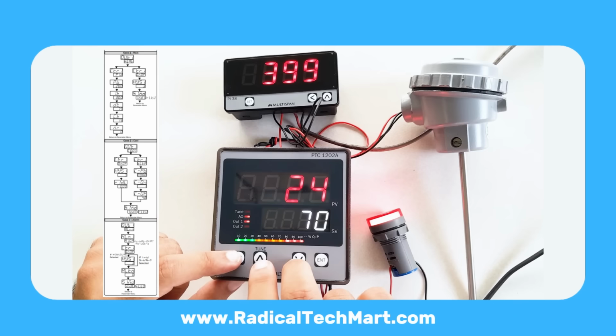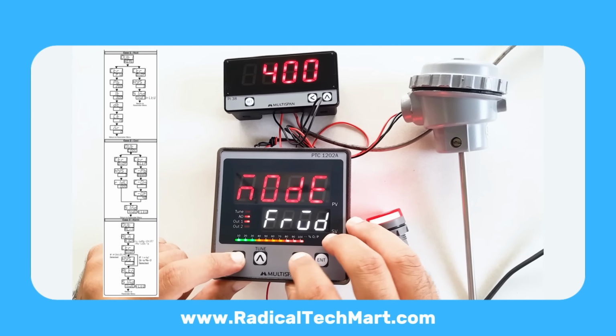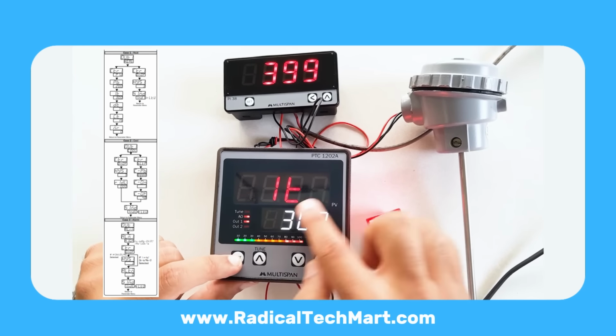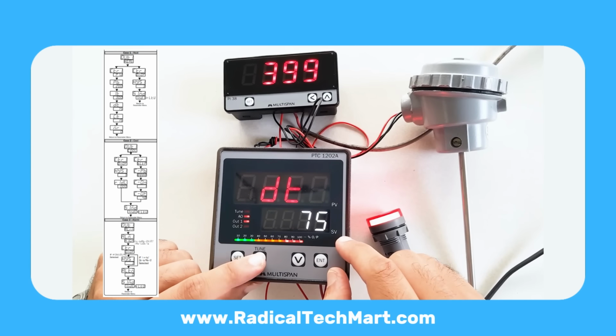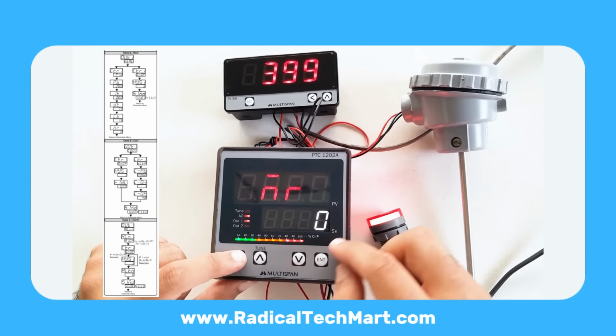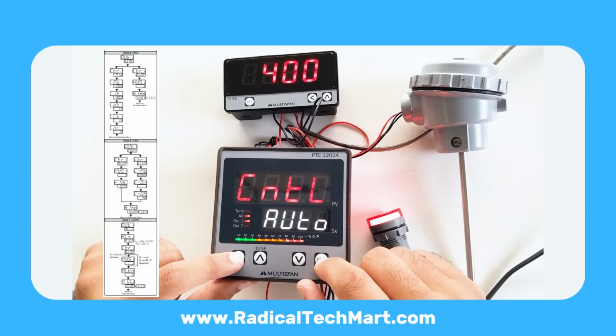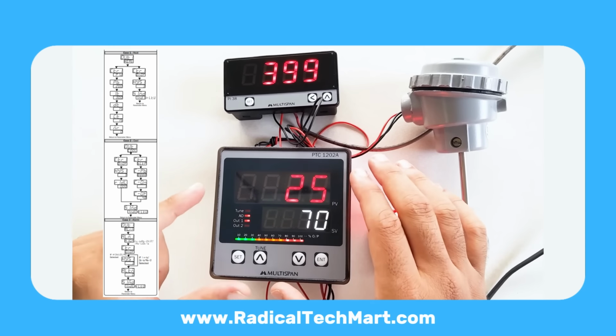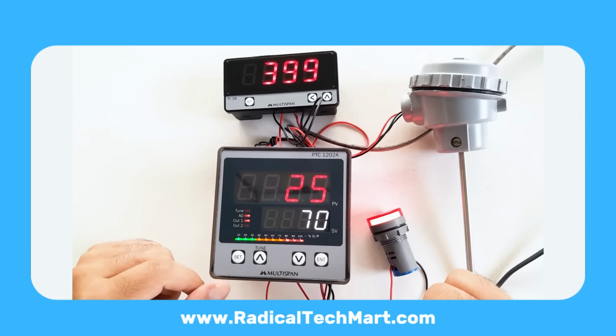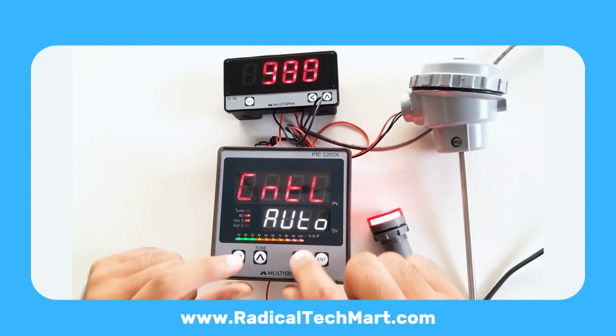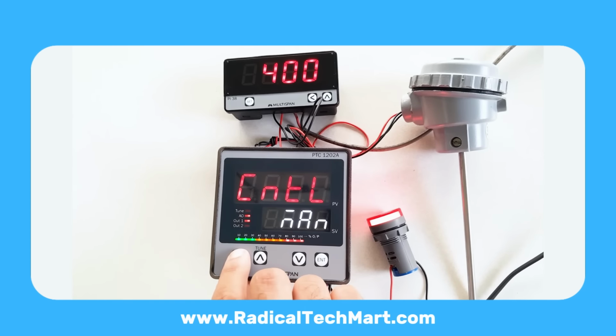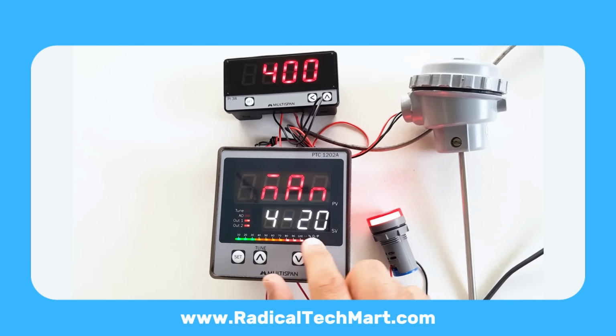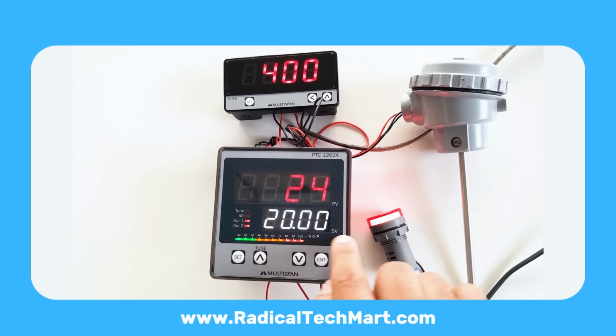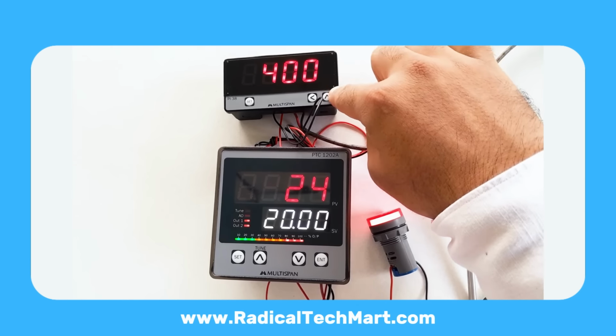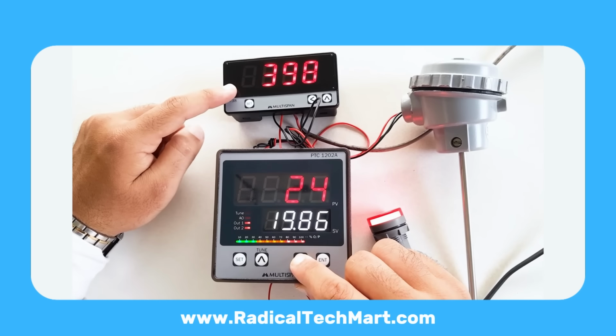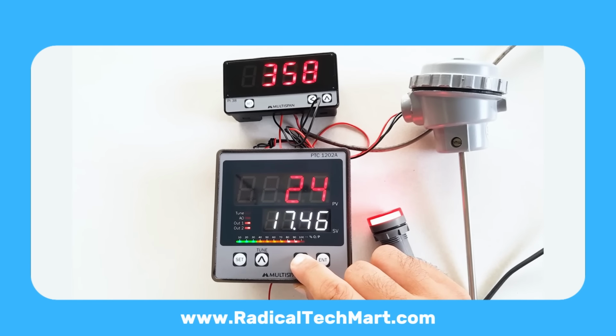PB, proportional band. I, integral time. D, derivative time. Cycle time, for time proportioning relays, SSR if used. MR, manual reset, bias. Press enter to save. If you just need a static 4 to 20 mA source, switch auto to manual. Then choose 4 to 20 mA or percent. In 4 to 20 mA, set 20 mA, Pi38 shows about 400, set 12 mA, about 200, set 4 mA, 0. Perfect for loop checks and calibration.